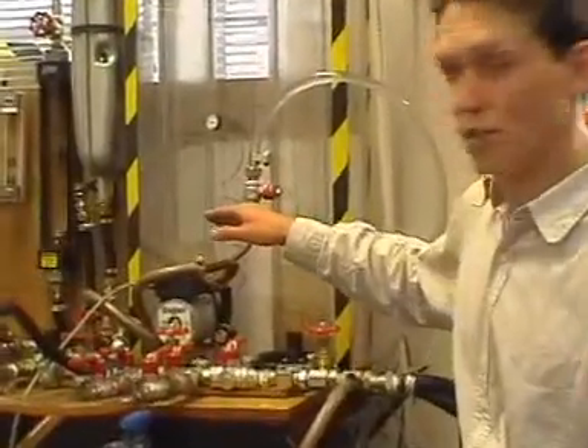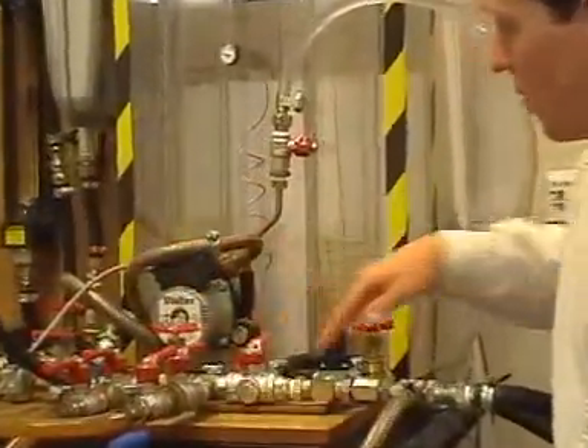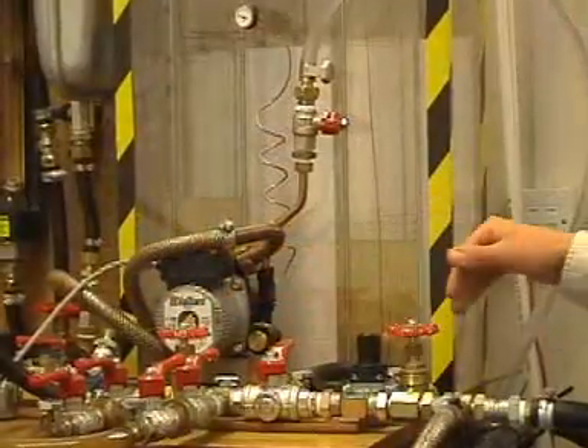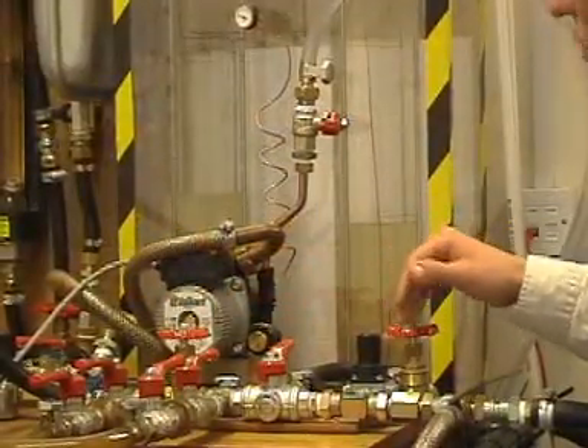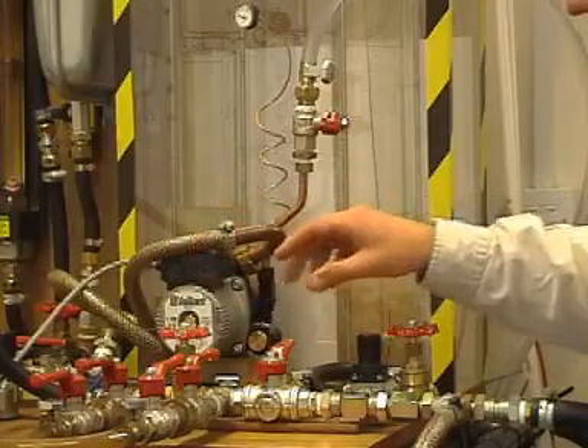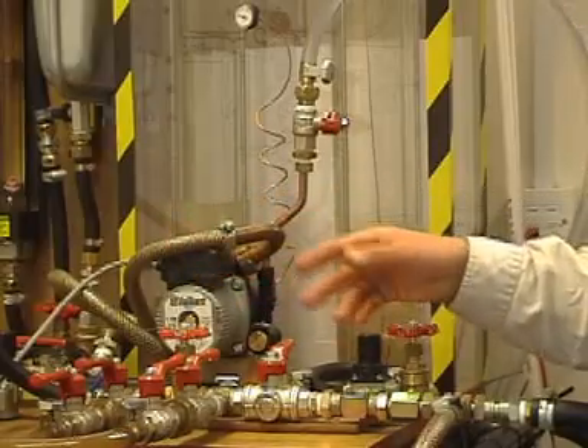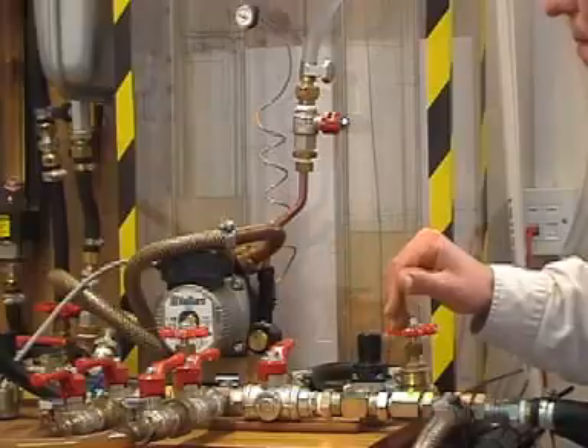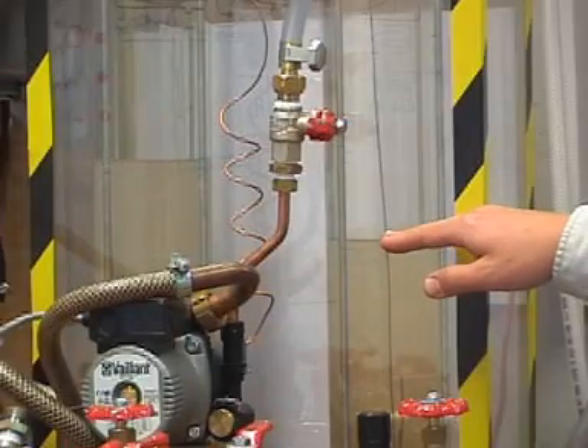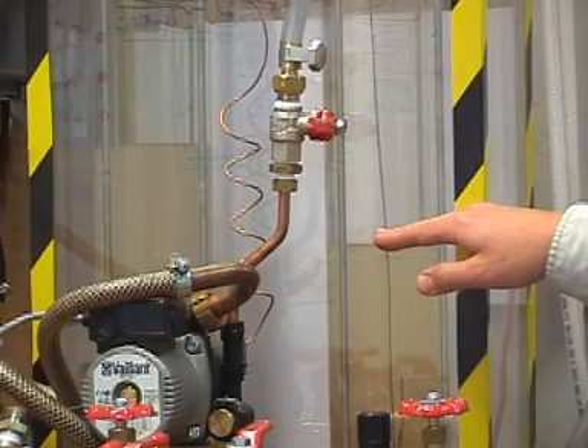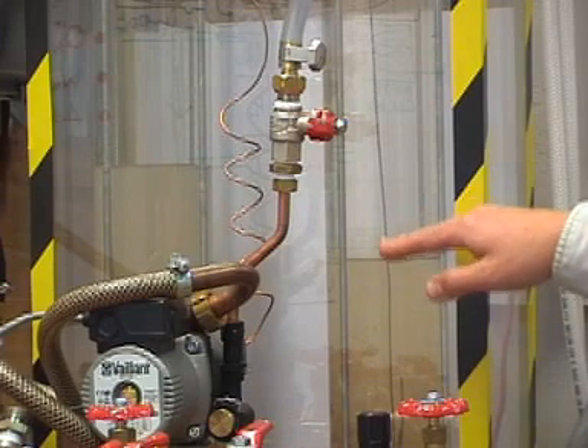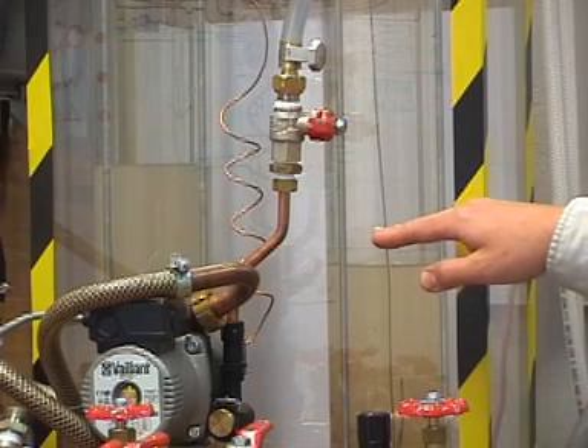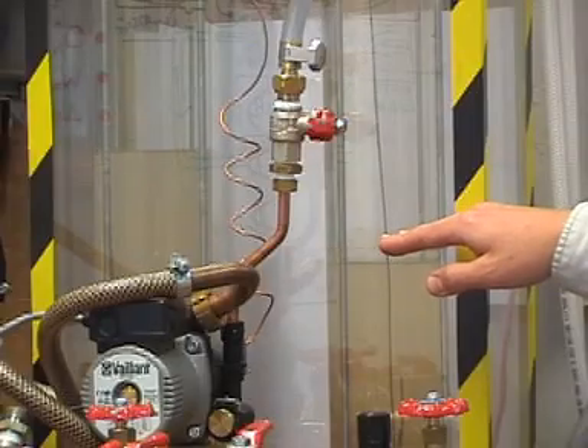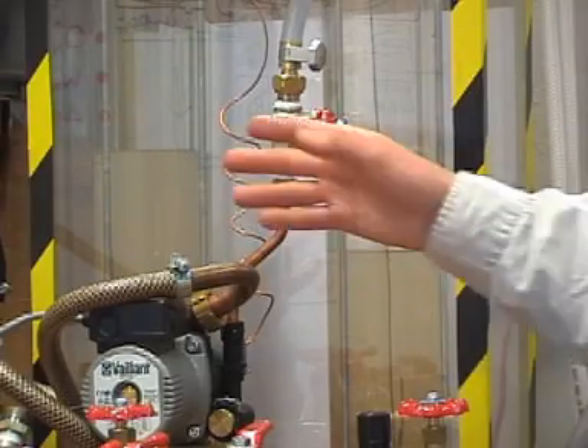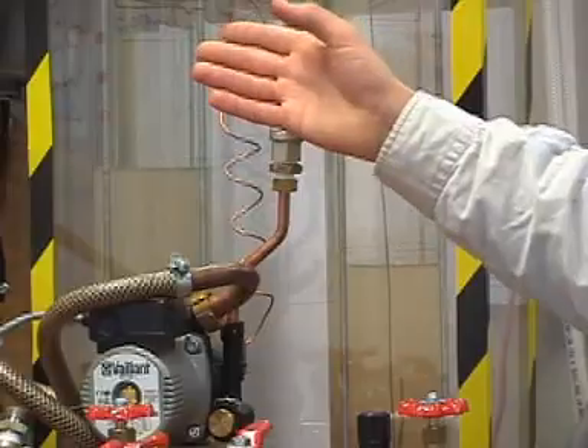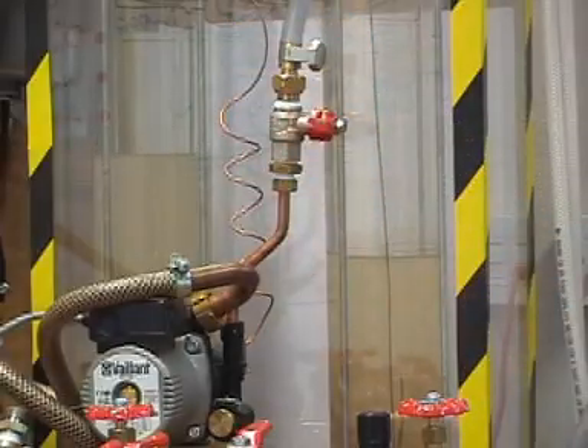The resulting pressure difference drives an approximately steady flow through the rest of the system, which represents the household full of radiators. And we can change these valves here to simulate different households and different flow conditions. If we look at the level of the liquid inside these reservoirs, we can see that the magnitude of the oscillation due to the NIFTE is very small. This serves as some indication that any disruption to existing components, such as the expansion vessel, is likely to be small.